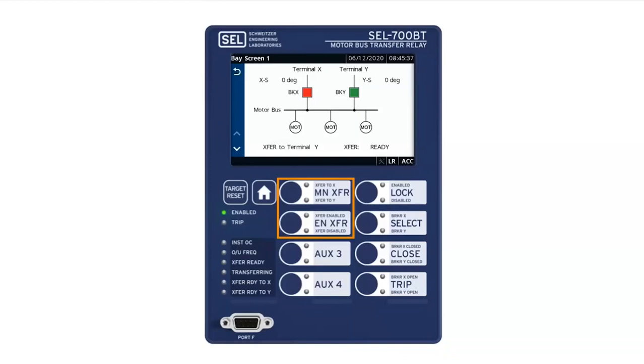Yeah, I can take that. So we do have a very successful application using our SEL 451 in the motor bus transfer application. The benefit of having 700 BT is it is a smaller form factor, and it comes with inbuilt logic. So with SEL 451, we do many hours of system study, the parameter study, and then build a complex logic equation to do the motor bus transfer application. In 700 BT, we have inbuilt logic, which simplifies the customer side of using this product in that application. Because as we showed in one of our slides, how simple the settings are. You do a simple system study and then you put the settings together. You don't have to build a complex logic equation to put this product in the application.